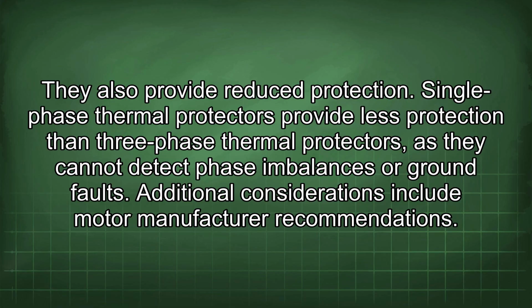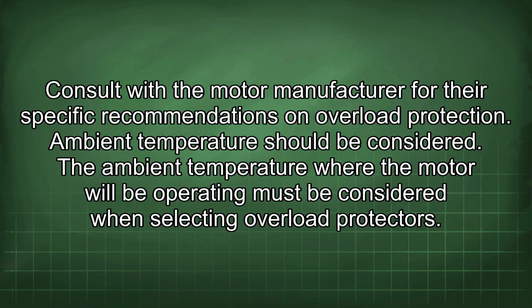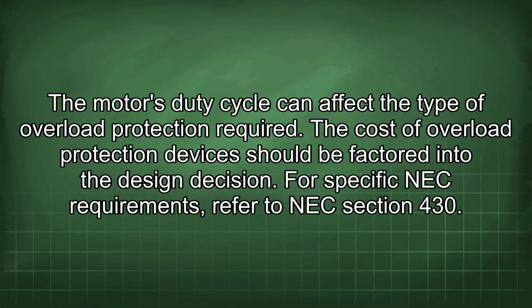Additional considerations include motor manufacturer recommendations. Consult with the motor manufacturer for their specific recommendations on overload protection. Ambient temperature should be considered. The ambient temperature where the motor will be operating must be considered when selecting overload protectors. The motor's duty cycle can affect the type of overload protection required. The cost of overload protection devices should be factored into the design decision.